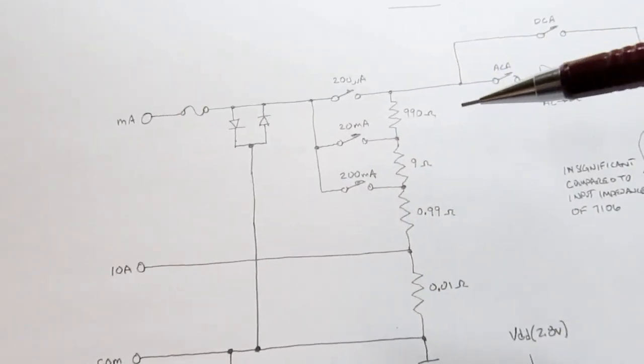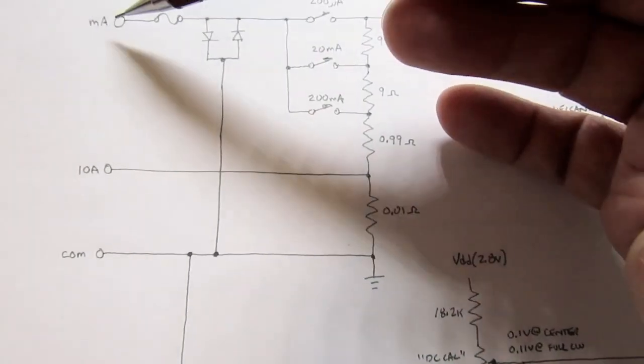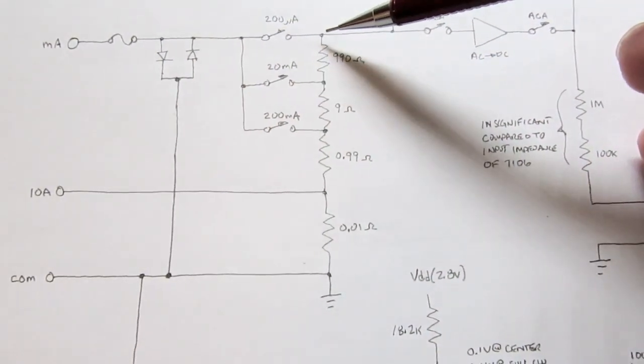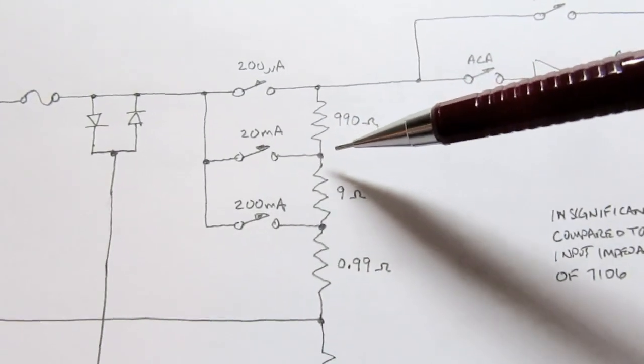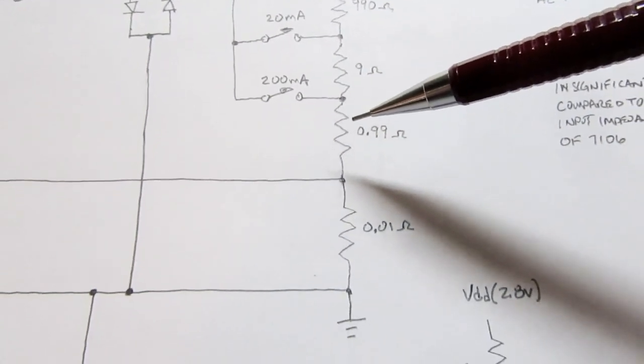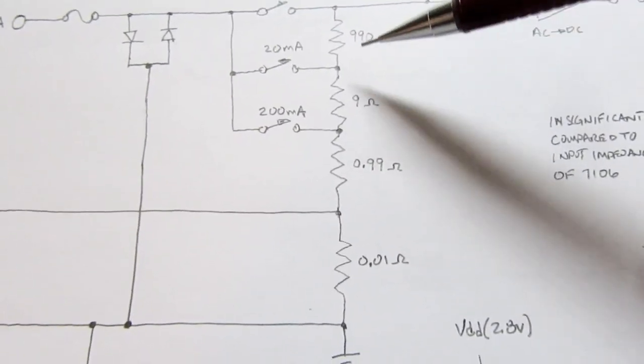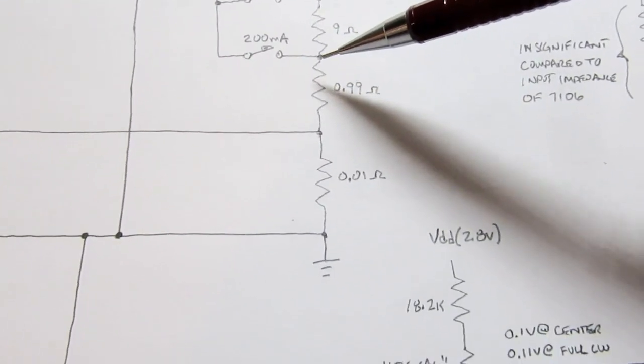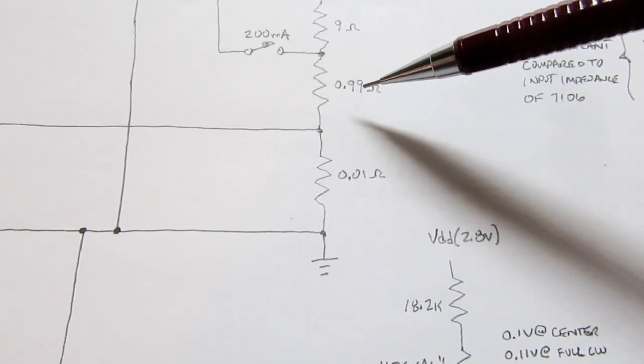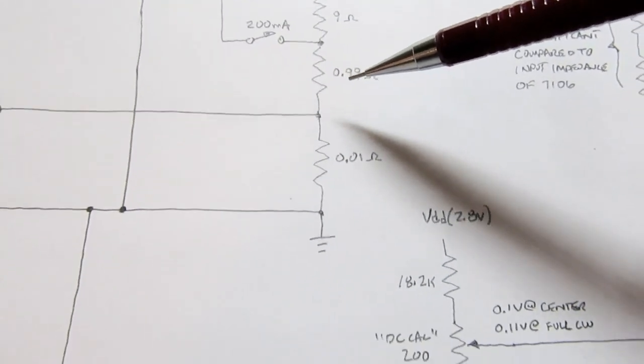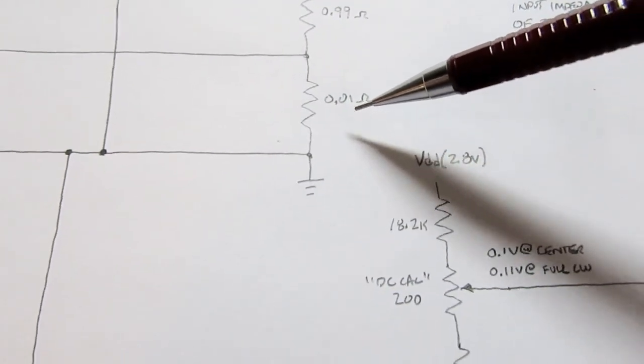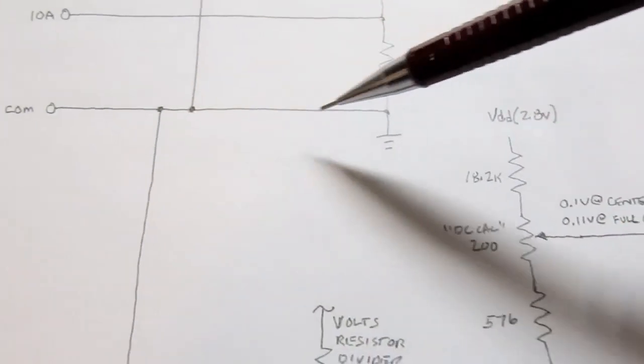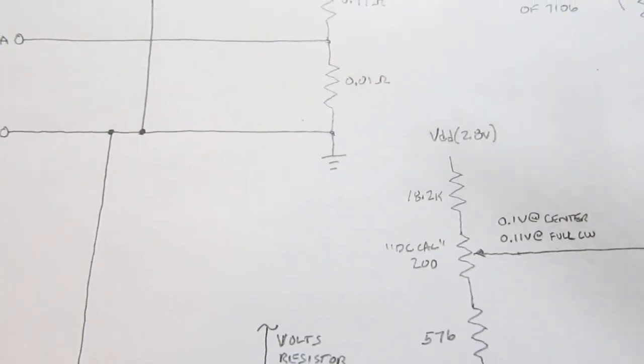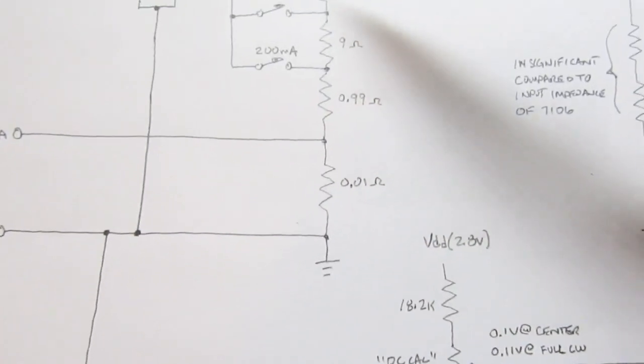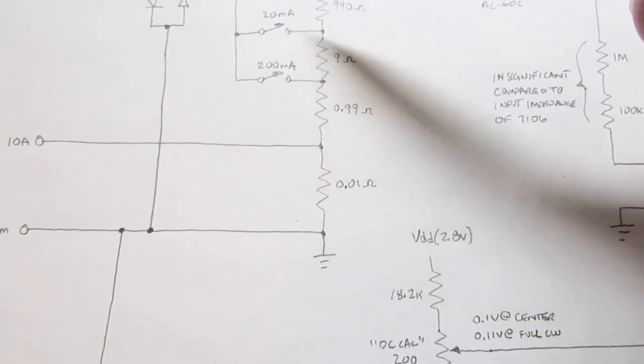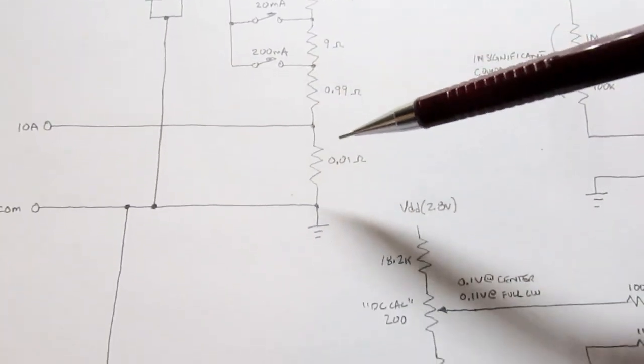So let's look at situations where we don't have an overload. We come in here with our milliamp signal. It goes through a big shunt resistor made out of a 990 ohm, a 9 ohm. There's a couple orders of magnitude difference there. And then a 0.99 ohm, so it's almost 1 ohm. And then a 0.01 ohm, and then back to circuit common. If you add all those up, that becomes 1K, 1 kilo ohm, 1000 ohms across the entire shunt.